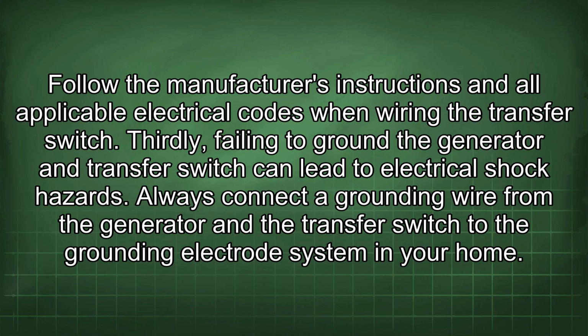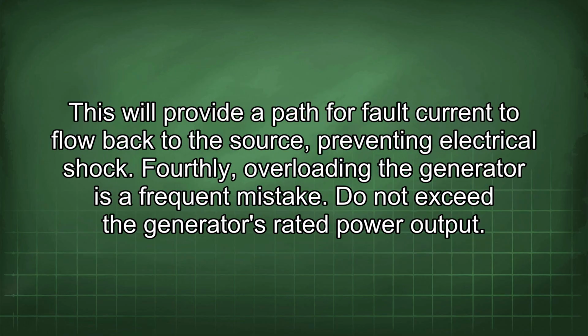Thirdly, failing to ground the generator and transfer switch can lead to electrical shock hazards. Always connect a grounding wire from the generator and the transfer switch to the grounding electrode system in your home. This will provide a path for fault current to flow back to the source, preventing electrical shock.